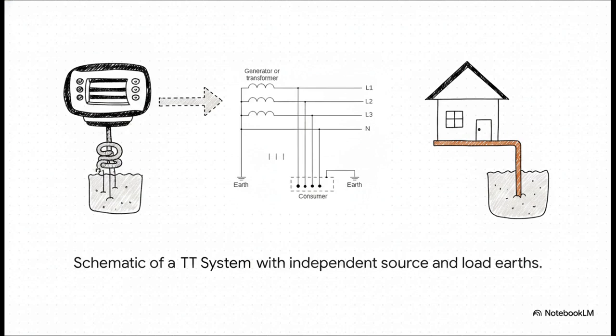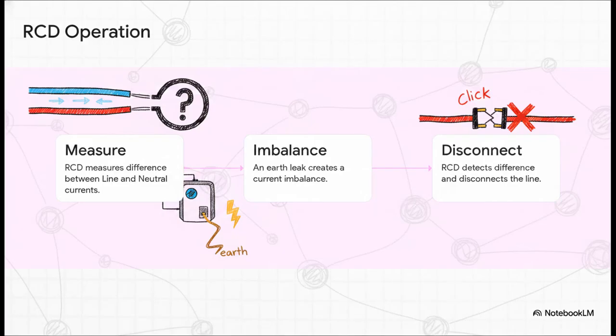They are totally independent. The only things the utility company is sending down the line to you are the live and neutral wires. But there is a catch with the TT system. Because you're relying entirely on the local dirt in your backyard for your safety path, the fault loop impedance can actually be quite high. Let's be real, dirt isn't a perfect conductor. This means a dangerous earth fault might not actually generate enough current to flip a standard old-school circuit breaker. So, TT systems bring in a highly sensitive bodyguard called an RCD, or residual current device.